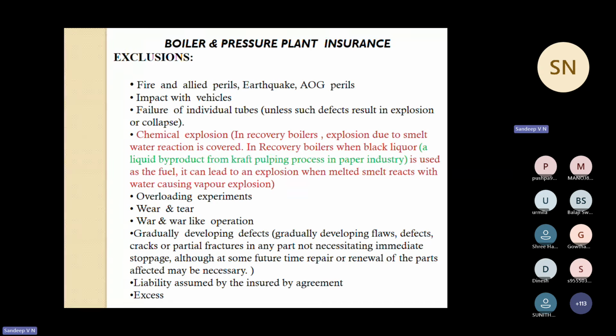Then a chemical explosion is not covered. Now there is one point here. Boilers are of different types. I was talking about fire tube boiler and water tube boiler. There is another boiler known as waste heat recovery boiler. Rate also varies with the type of boiler. In the case of the paper industry, after the pulping process, which is known as the kraft pulping process, there is a byproduct coming out which is known as black liquor. This black liquor is used as a fuel in boilers. When black liquor is used as a fuel, there can be an explosion, which is known as smelt water reaction.